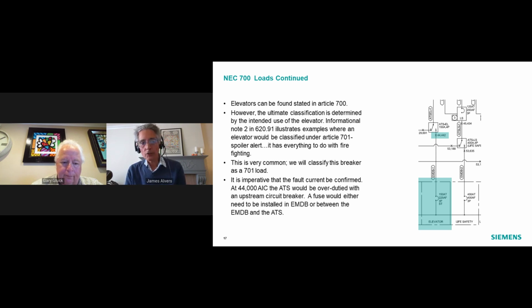So elevators are actually specifically mentioned in Article 700, but as Gary mentioned, they often fall into Article 701 because they are used for first responders. So that is something that comes out of the informational note in Article 620.91. So this is very common, and in this particular example, we're going to classify the elevator breaker into a 701 load. Once again, let's look at fault current.